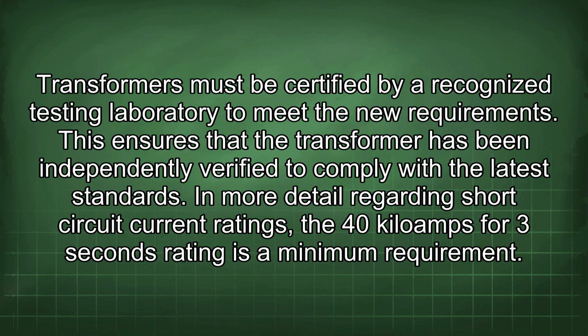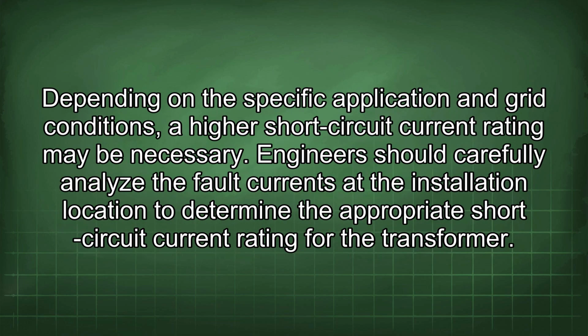In more detail regarding short-circuit current ratings, the 40 kA for 3 seconds rating is a minimum requirement. Depending on the specific application and grid conditions, a higher short-circuit current rating may be necessary. Engineers should carefully analyze the fault currents at the installation location to determine the appropriate short-circuit current rating for the transformer.